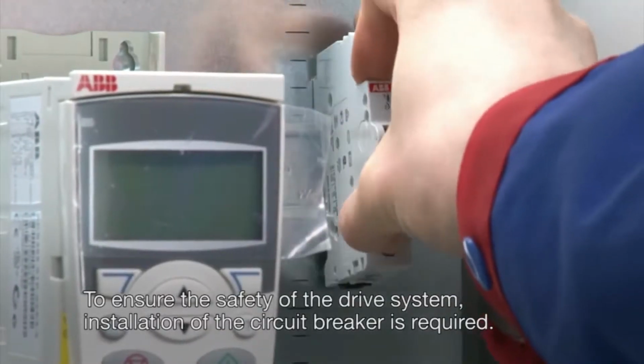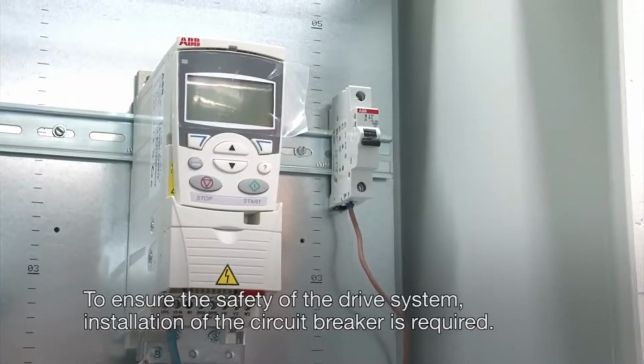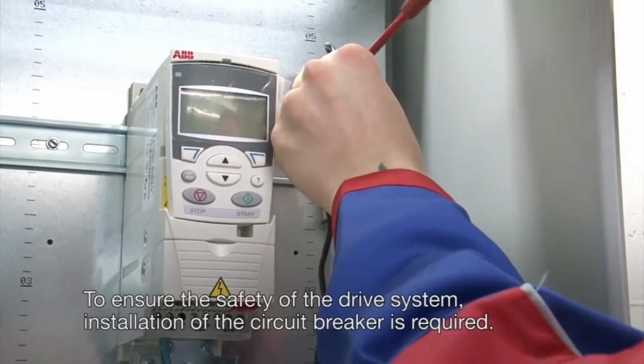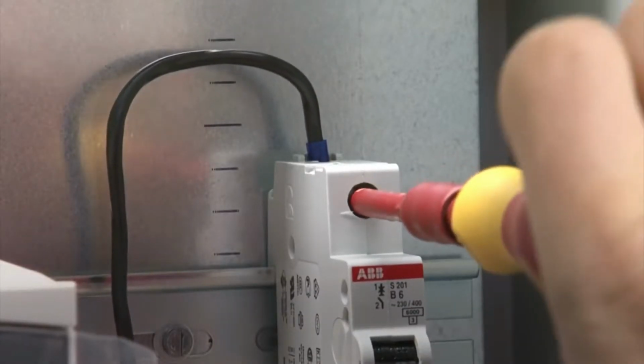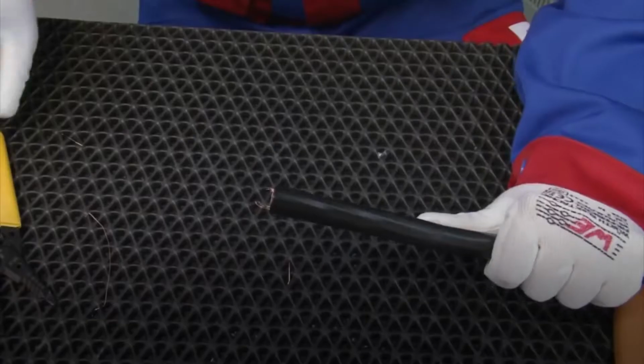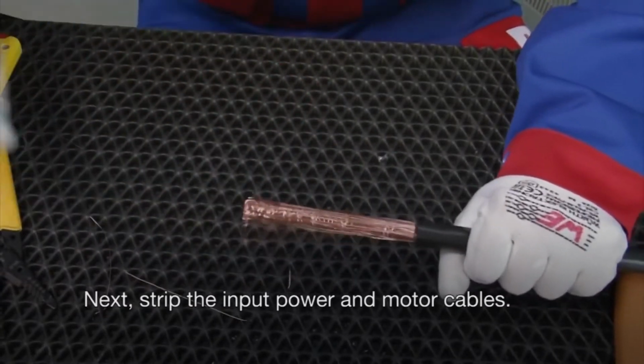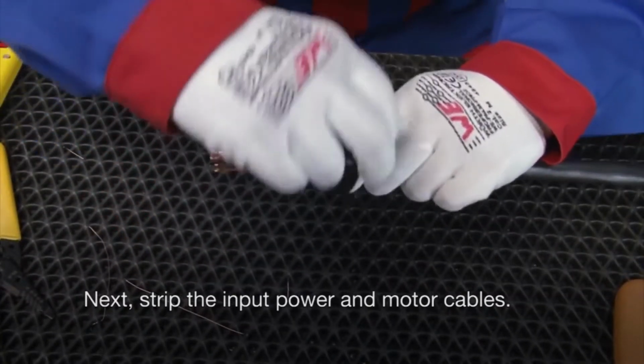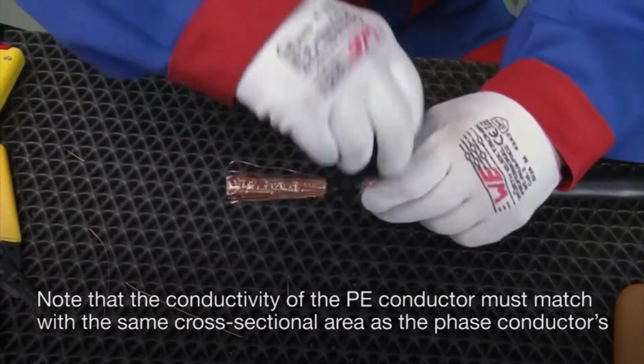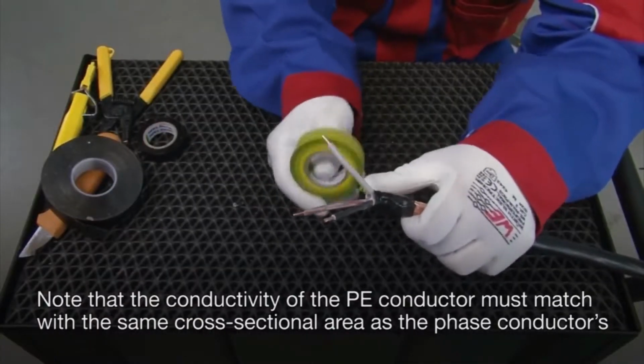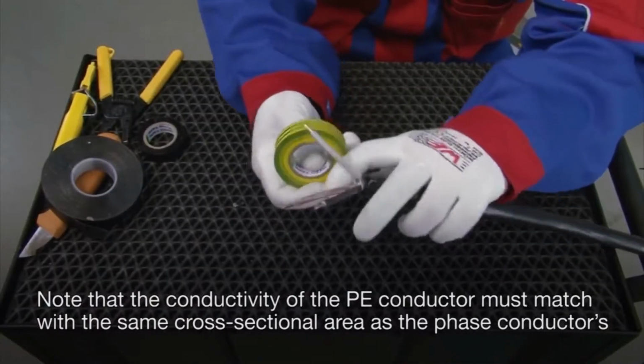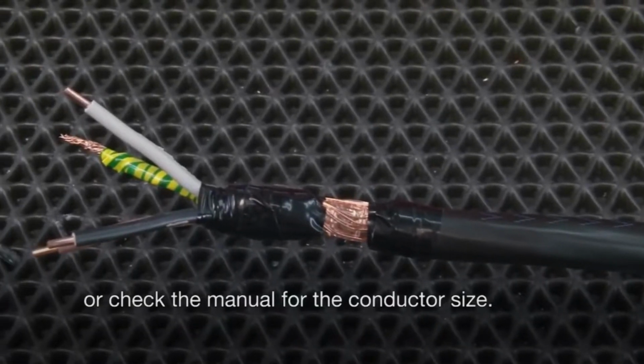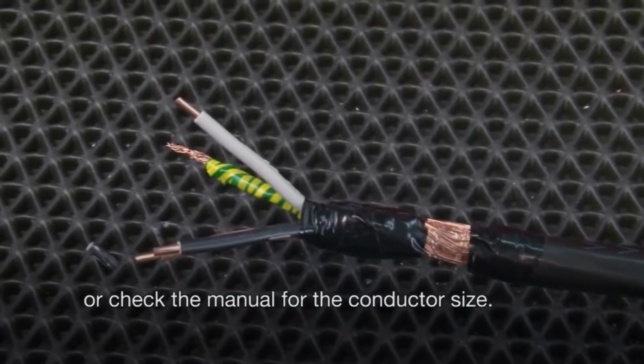To ensure the safety of the drive system, installation of the circuit breaker is required. Next, strip the input power and motor cables. Note that the conductivity of the PE conductor must match with the same cross-sectional area as the phase conductors, or check the manual for the conductor size.